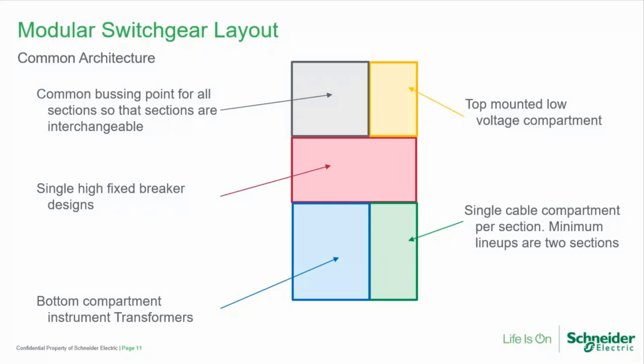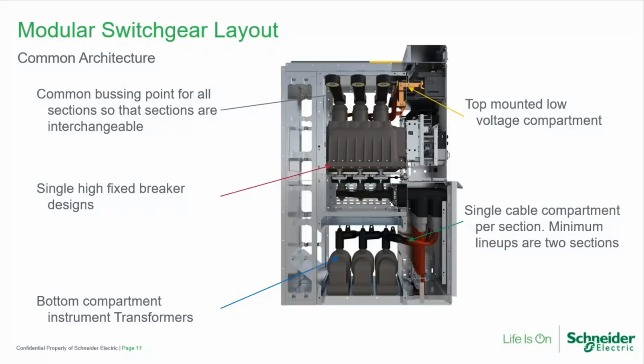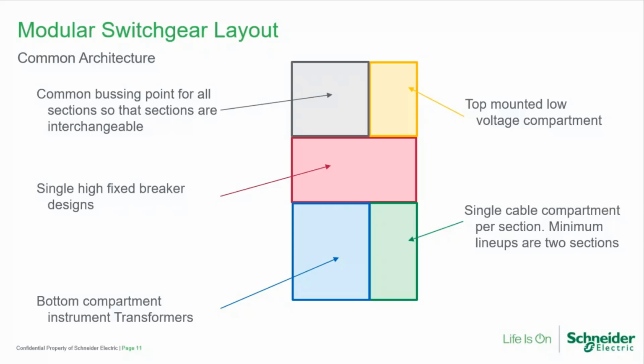So I've mentioned several times this idea around a modular switchgear architecture in terms of the lineup. I'd also like to mention that this is very true in terms of section to section design. If you're looking for a similarity of types of cubicles, it's very easy to find this in the newer styles of medium voltage switchgear, GIS and SIS. Common busing points, common positions of low voltage compartments, a common point for the fixed mounted circuit breaker, similar positions for cable entry and instrument transformers.